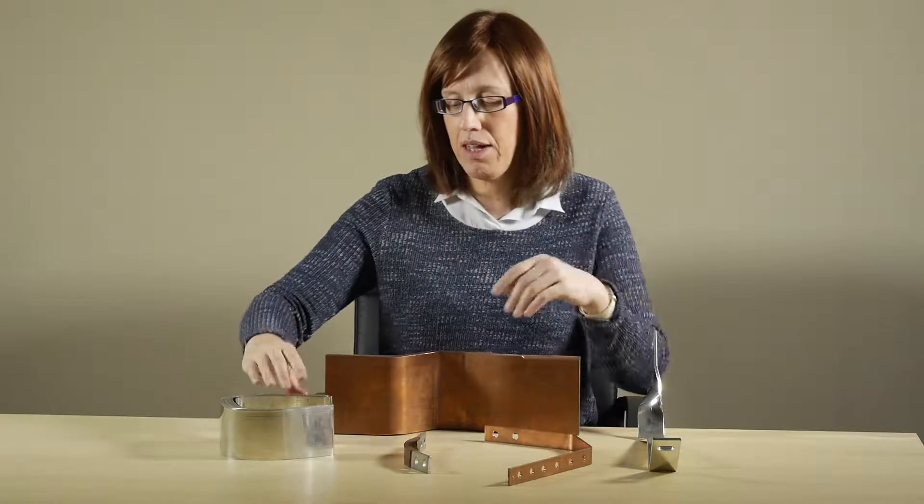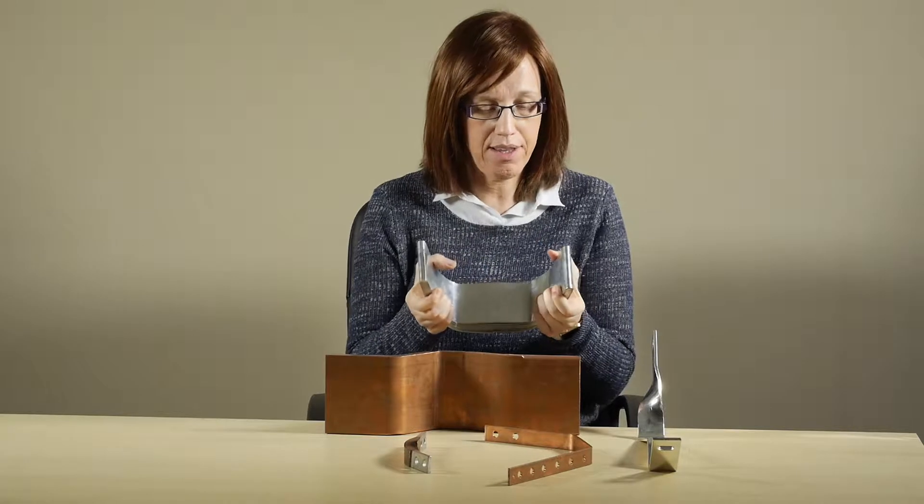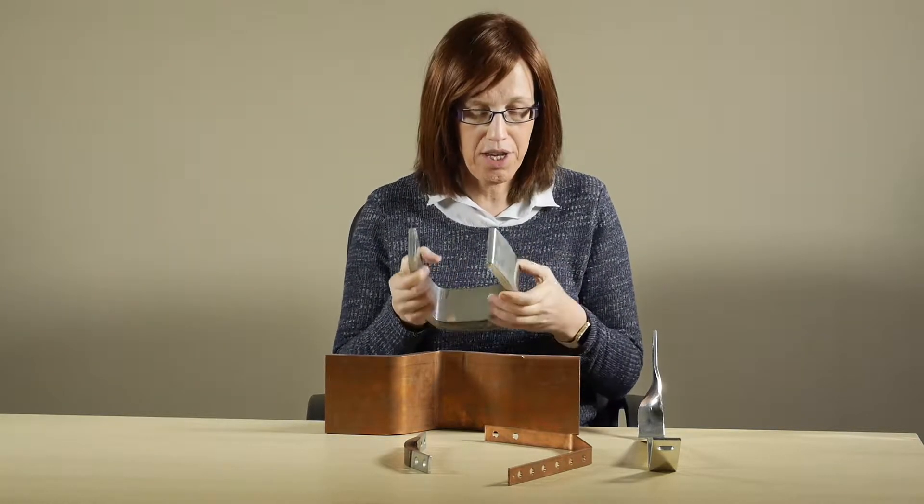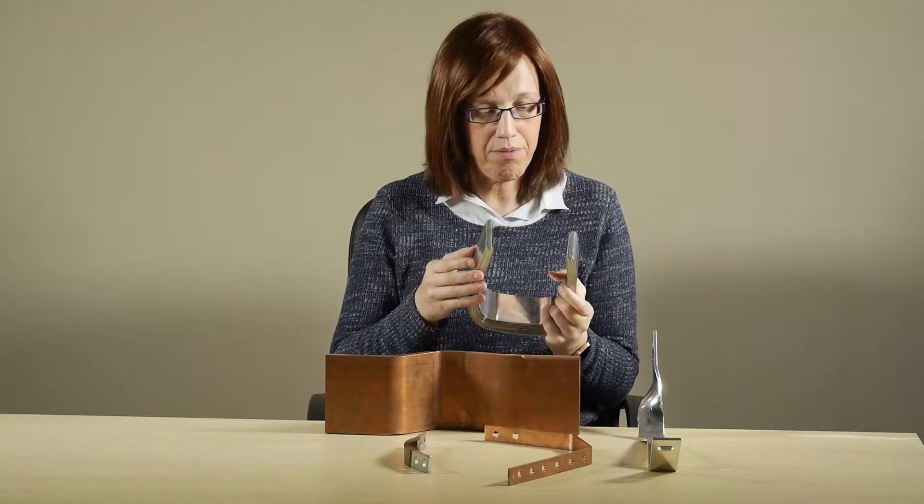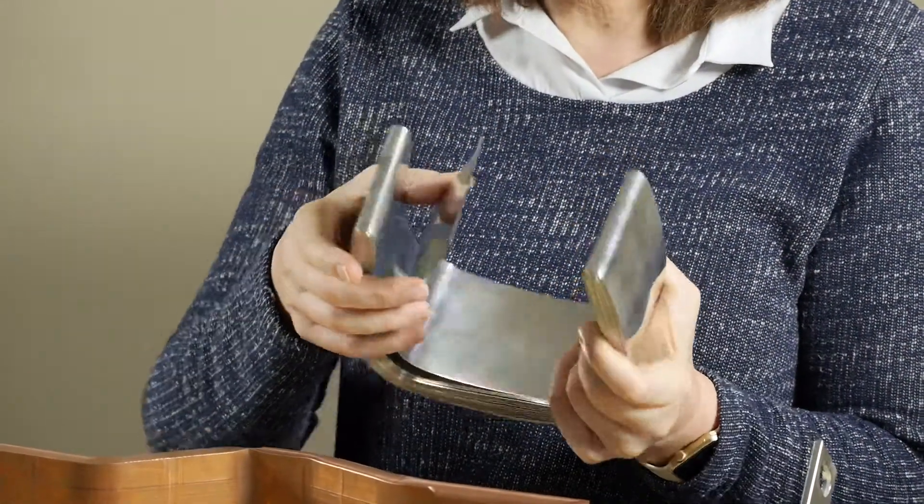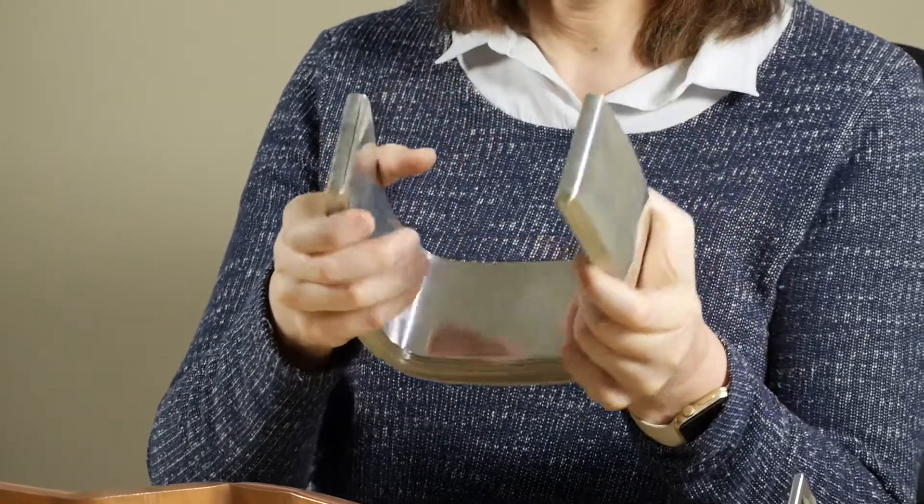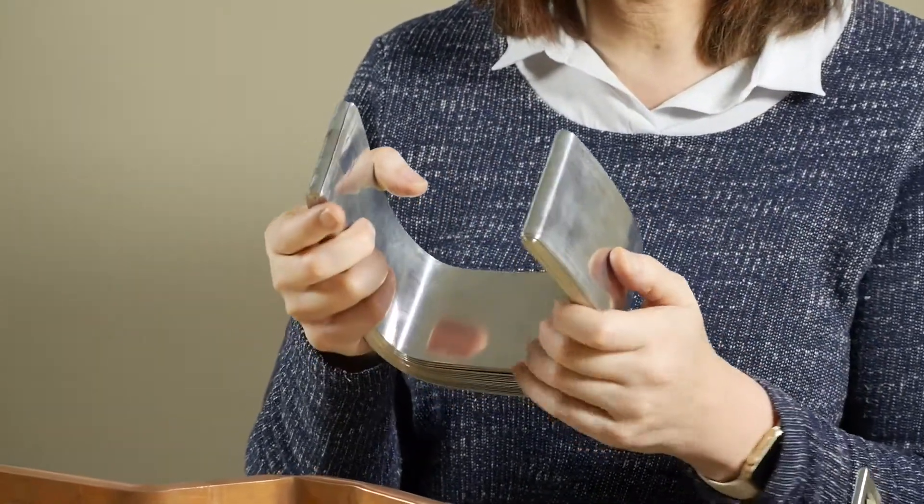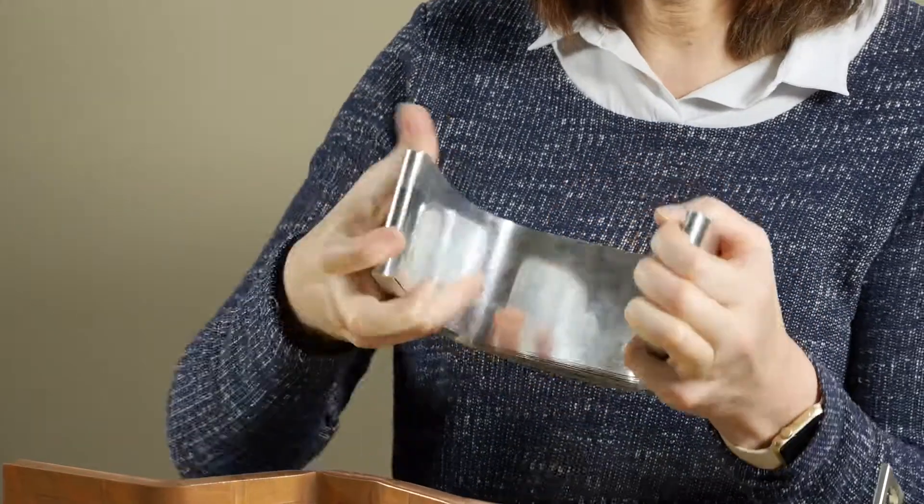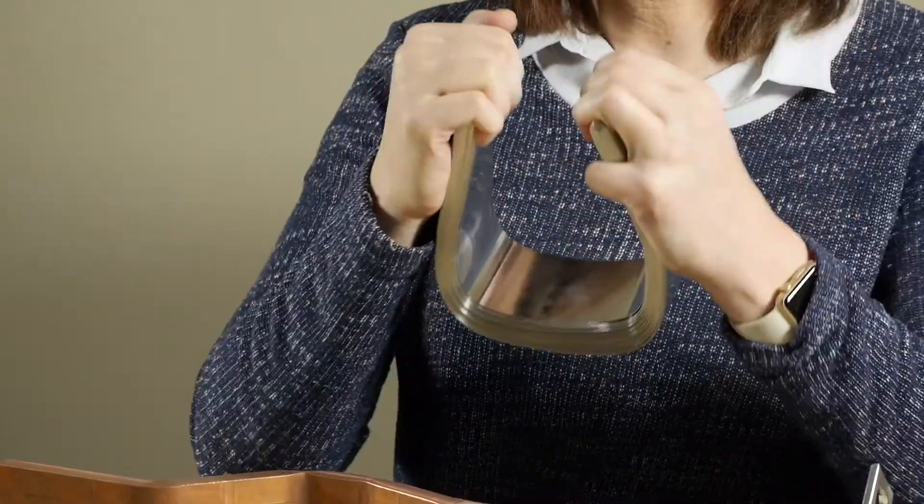We do small ones like that and also big ones like this. This is from high voltage switchgear and it's made up of many layers of copper foil. You can see here we wrap them around so the ends are locked in, and this gives the copper busbar the ability to flex continuously in operation without breaking the copper.